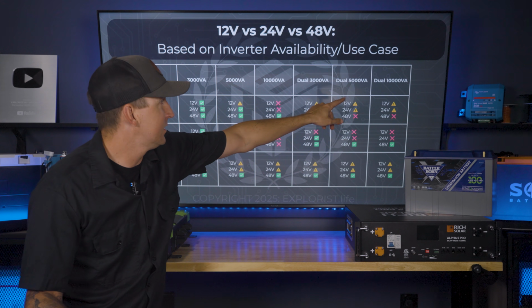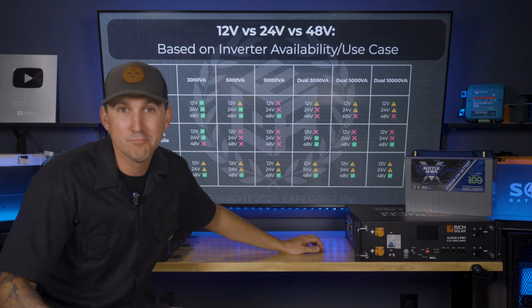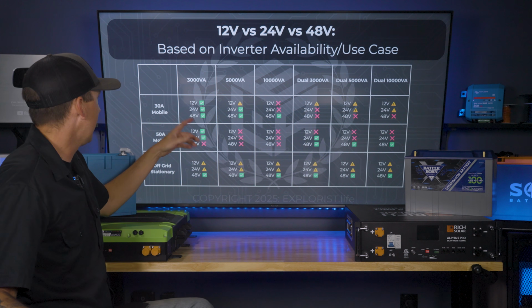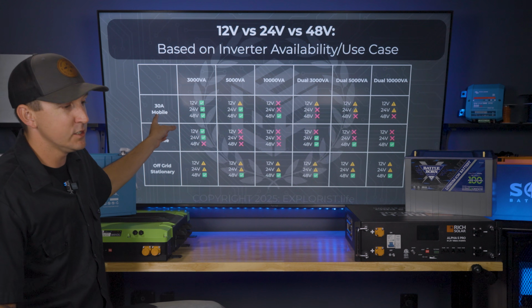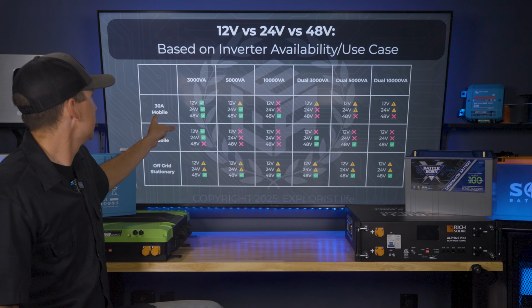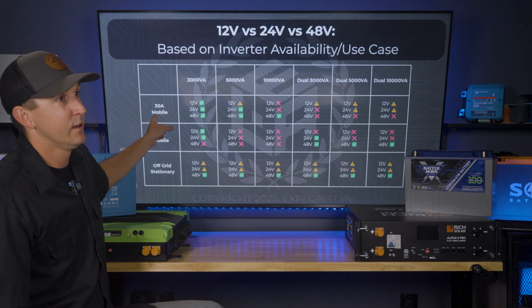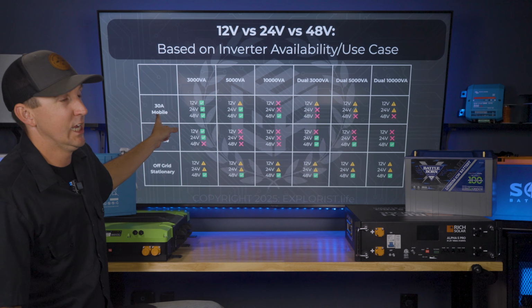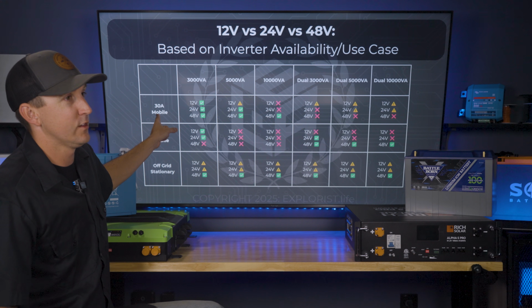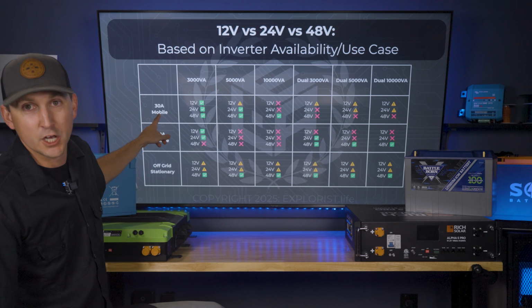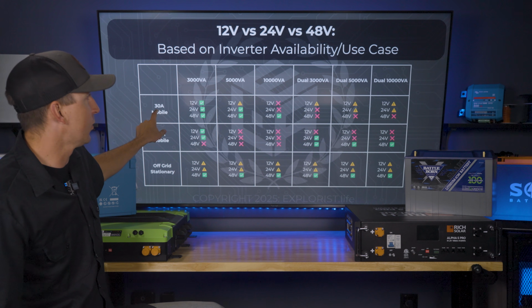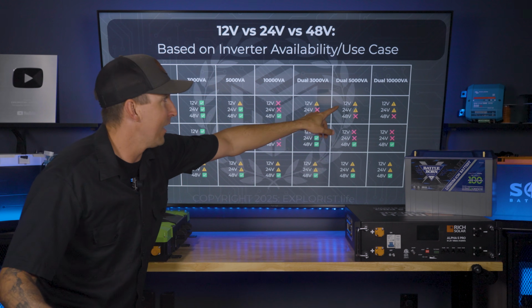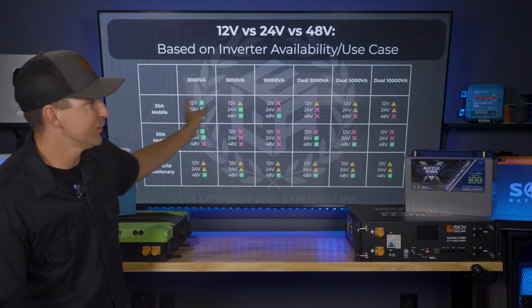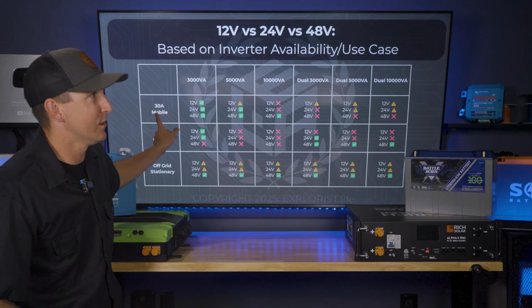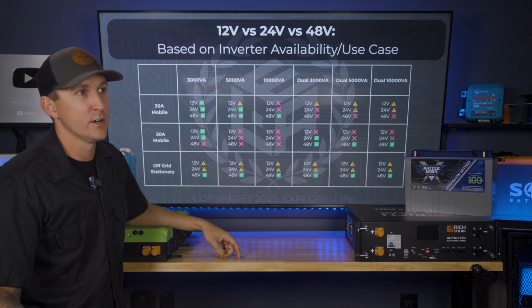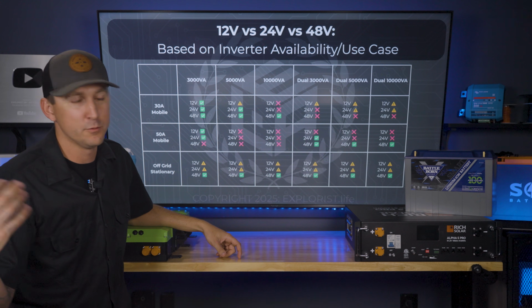In a dual 10 kVA system, like 20,000 watts of power on a 30 amp mobile application - hey Steph, quick math, 30 times 120. 3,600. So that's 3,600 watts of power coming in from shore power. Realistically, having dual 10 kVA inverter chargers on a 30 amp setup is way more power than the breaker box can handle, and you're going to start tripping breakers if you ask it to pull that much power.